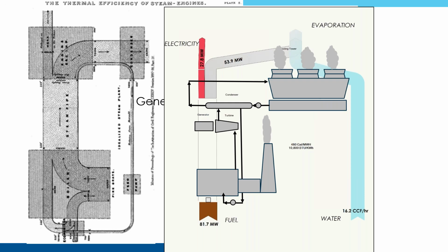It's kind of startling to look at that. These power plants are only about 30, 32, maybe 35% efficient. Which is to say, of the energy that comes in, only 35 of the 80, 81 megawatts coming in, we're able to actually get 27 megawatts out on the grid, on the wires going out to the communities. The rest, this 53 megawatts, has to be dissipated. We've got to get rid of that.